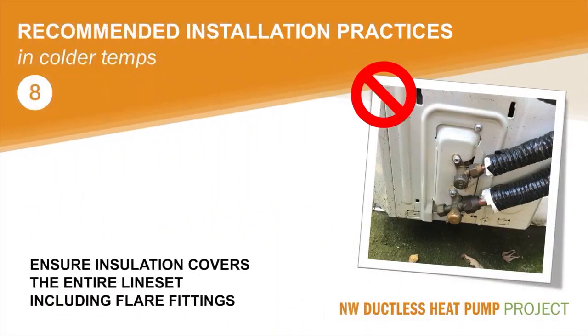Our next recommended installation practice is to ensure insulation covers the entire line set, including the flare fittings. Manufacturers recommend that every installation have the line set completely covered with insulation, and that the insulation remain intact for the useful life of the unit. Make sure the insulation covers the flare nuts as well as the entire line set length. This ensures liquid or frost will not develop under the flare nut and cause cracks and ultimately loss of refrigerant. Full insulation coverage also retains heat and improves system efficiency.